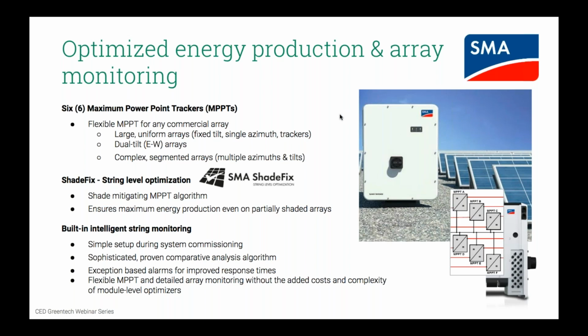Key features that deliver that in the Core 1: first, the inverter is designed with 6 independent maximum power point trackers, so you can connect 12 strings across these 6 MPPT trackers, each determining the maximum power point for the strings connected to it. This gives flexibility if the roof demands different string lengths in different sections, or in the case of east-west arrays like at King Open School, you can connect strings to different MPPT inputs and be sure you're getting maximum power from each section at any time of day.